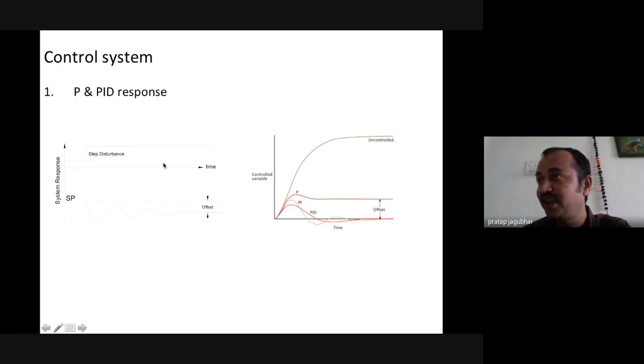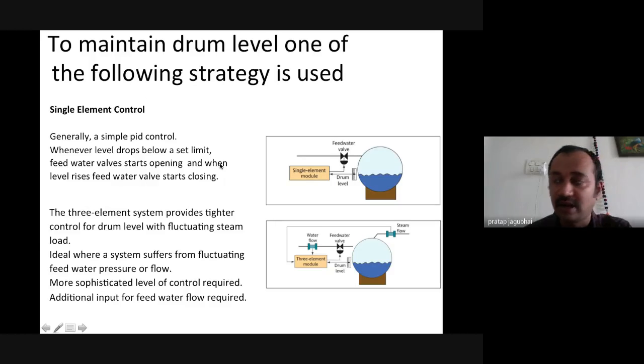Now that response can be available with the proportional action, but it's very difficult to adjust the error. So you can see we have given a disturbance in the form of a set point change, and the output is available with an offset. This error is difficult to minimize with only proportional action. For that, we need integral, which will reset the error. That's why it is called integral, and we can have a better response if we provide derivative also, so that the rate of change of error with respect to time will be minimized. So we can have a better output and better settling time for the response, and so better control is feasible. Now, to dwell more on the control side, let's start with the drum level control.